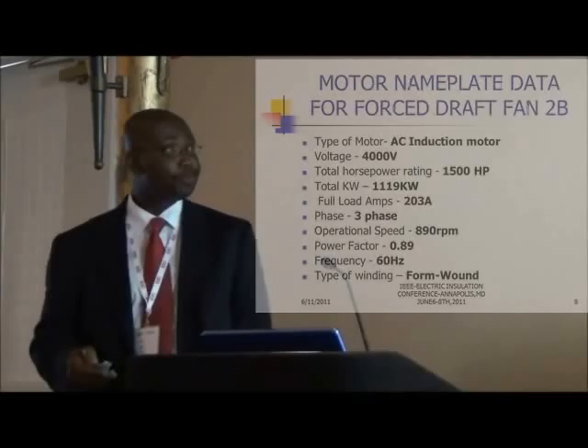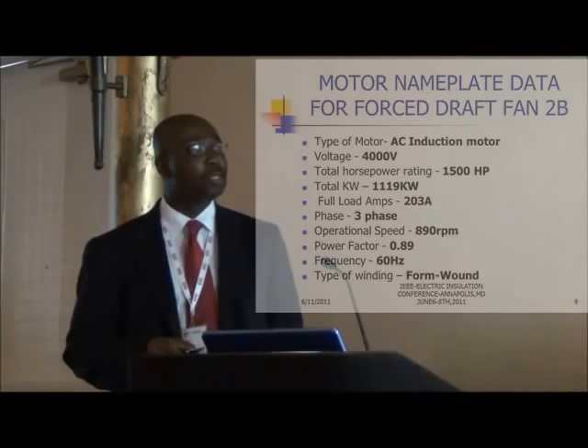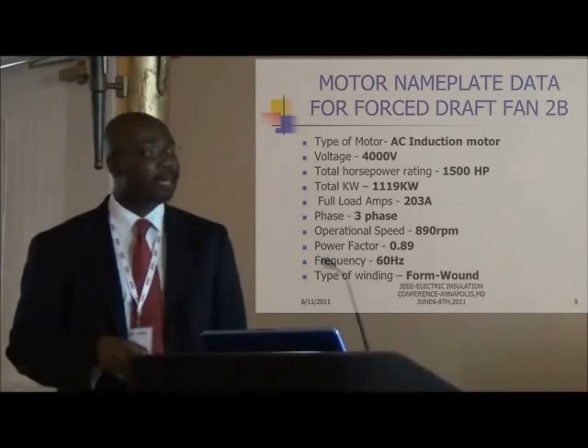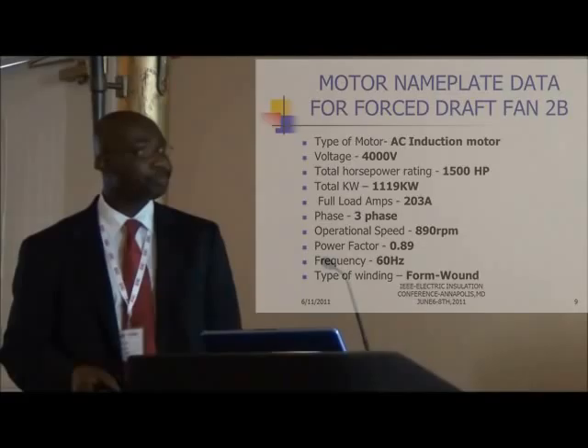The nameplate data for the force draft fan motor: it is an AC induction motor with a nominal operating voltage of 4,000 volts, a total horsepower rating of 1,500 HP (1,119 kW), full load amps of 203 amps, three-phase operation at 890 RPM, power factor of 0.89, and it is a form-wound motor.